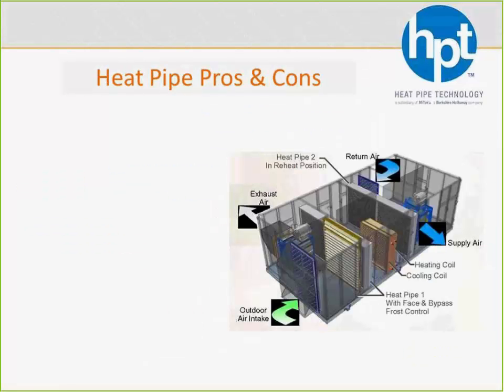So pros and cons. Believe it or not, there are some cons to the heat pipe. Yes, believe it, unfortunately, but they're very few. The biggest con is that we are a sensible only device. There are devices out there like wheels and fixed plates that recover latent heat, so when it comes to total enthalpy, they're going to outperform us, especially in the summertime where there is latent heat. When it's cold outside, we're still slightly less effective than the other devices, but now we're all sensible only anyway at that time, so we're not that much at a disadvantage. But in the summertime, you'll find that we are quite a bit less effective enthalpy-wise because we're not recovering latent heat when other devices are.